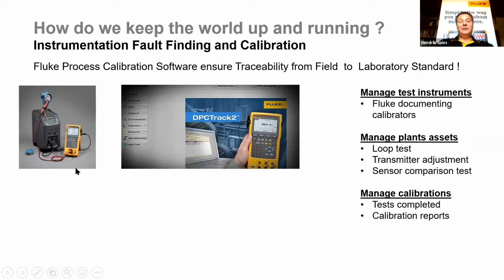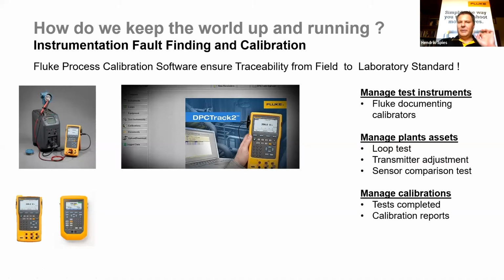And as you can see here, there's some PCT here where we've got a dry well where we are physically testing some temperature on a probe to a documenting multifunction calibrator. So what is important? We need to first manage the test instrument, the documenting calibrators, to see when they need to be calibrated to maintain the chain of calibration to the standard. The next thing is you're going to use this calibrator to actually calibrate an instrument in the plant. So you're managing your plant assets. So here typically you'll do loop testing, transmitter adjustment, some sensor comparisons.